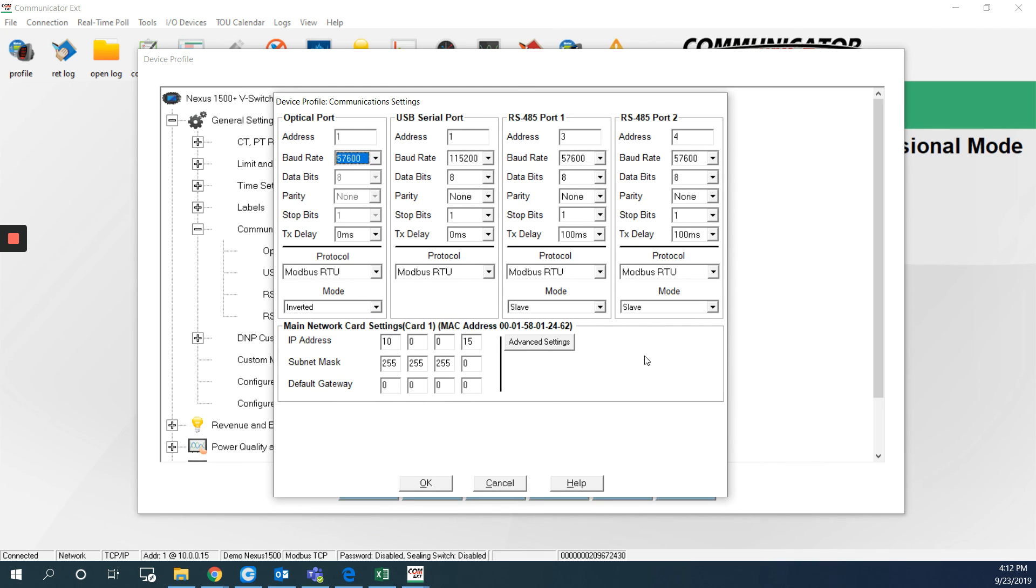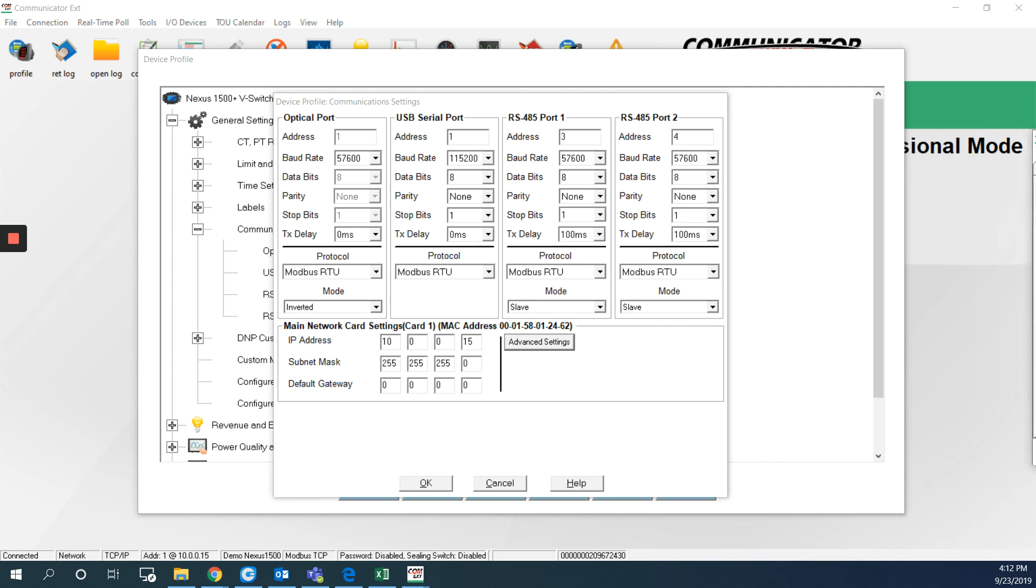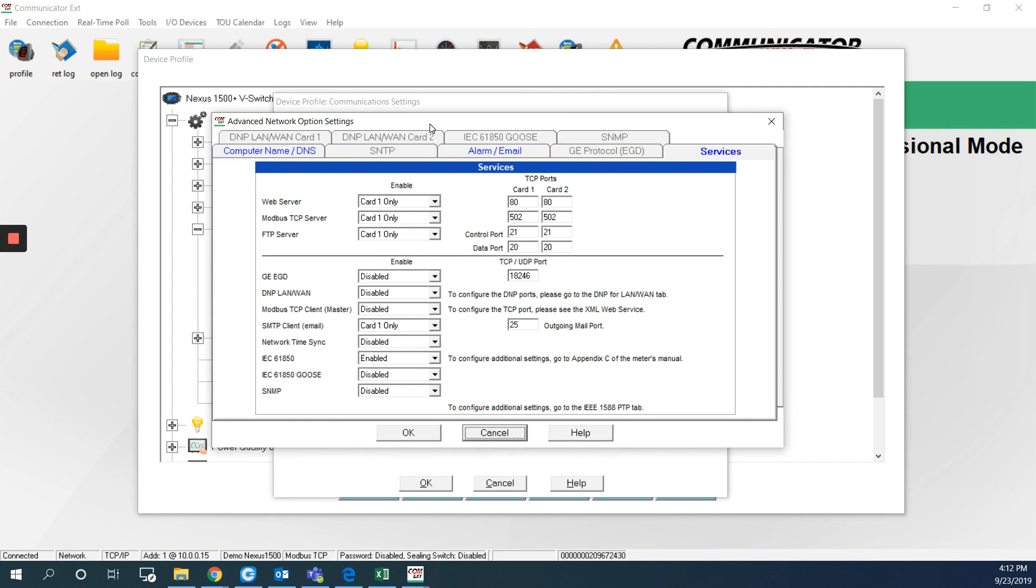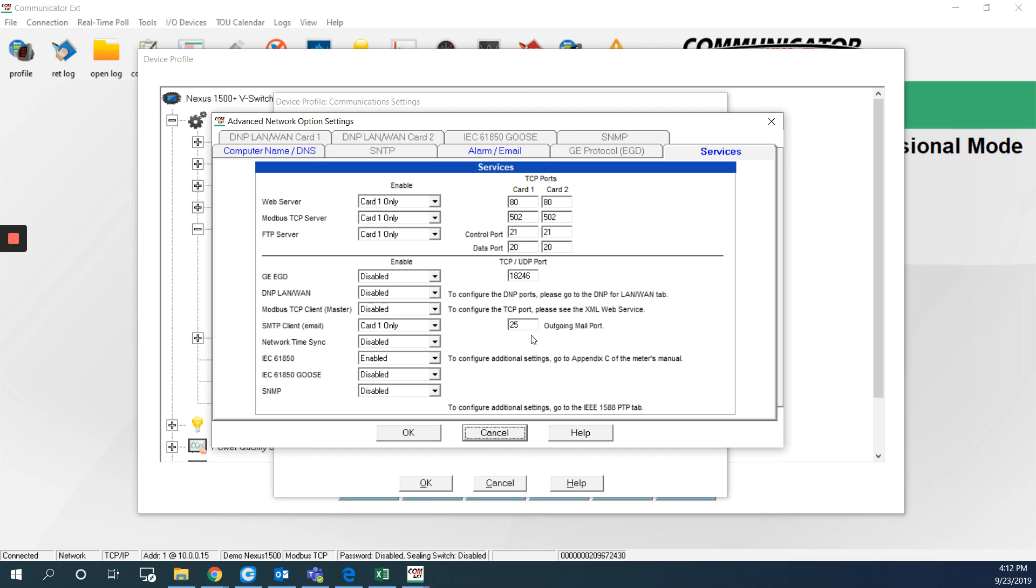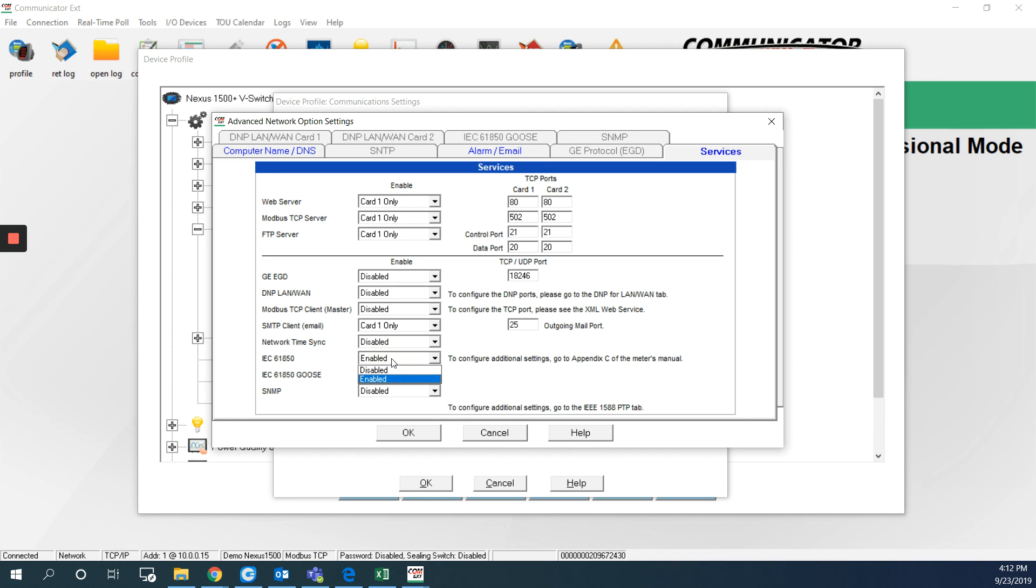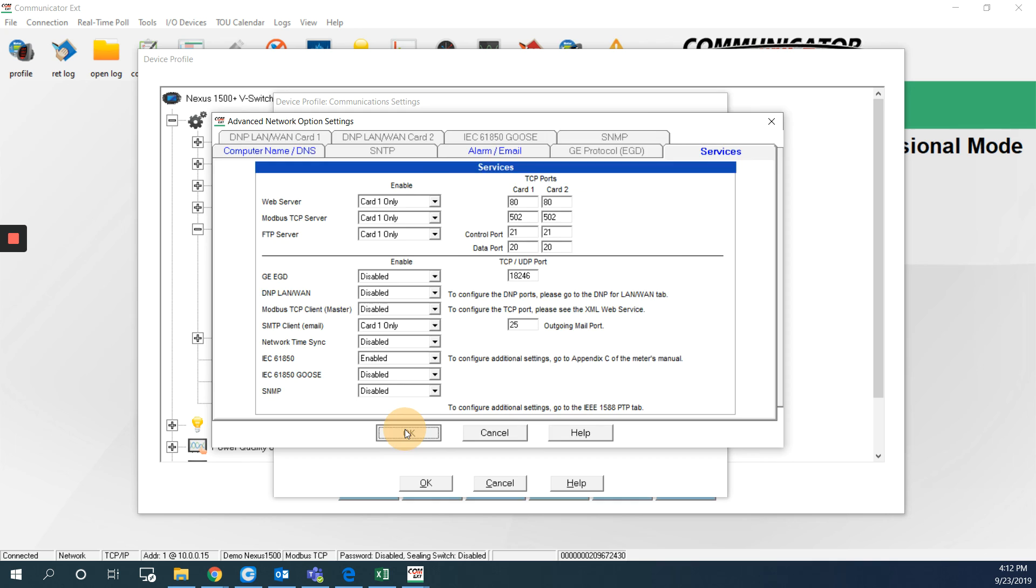The settings or the function I have to enable is on the ethernet port. So I will hit advanced settings. And I will get this window here. As you can see that IEC 61850 is enabled here at my meter. So if it was disabled, you just have to change this to enabled. Hit OK and hit OK again here.